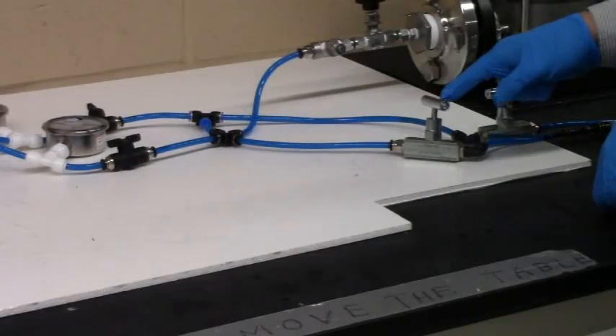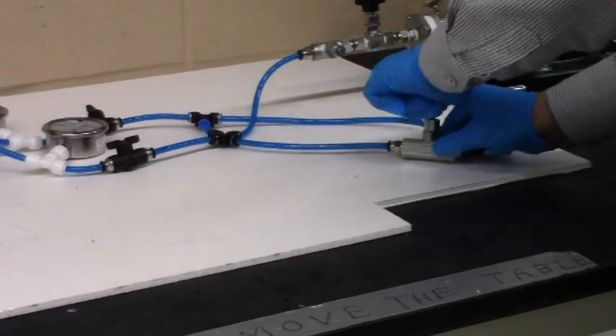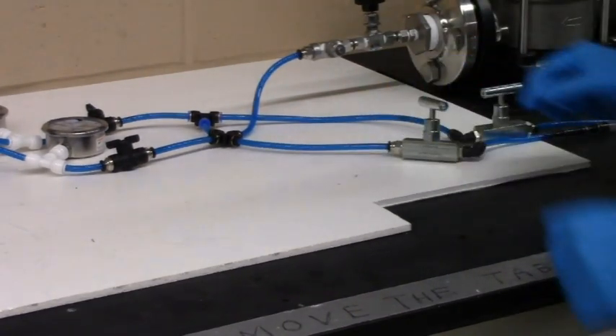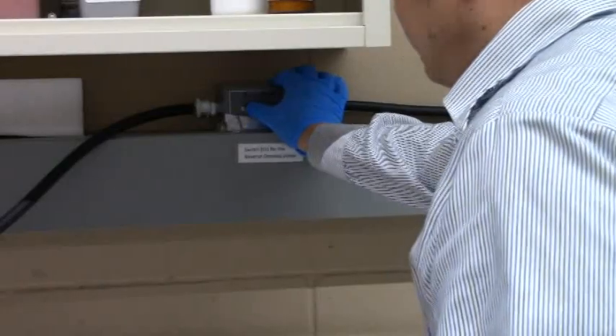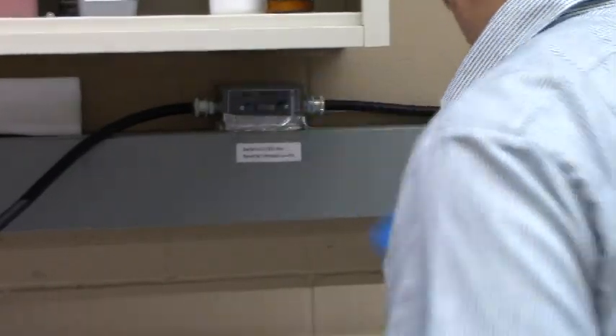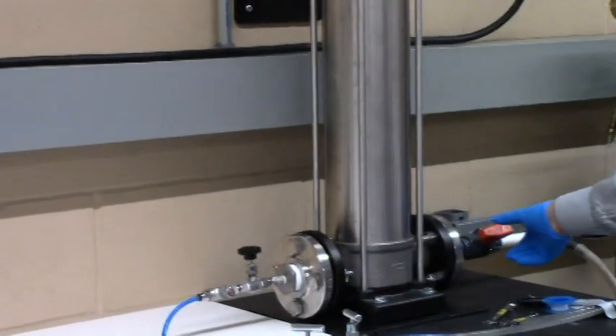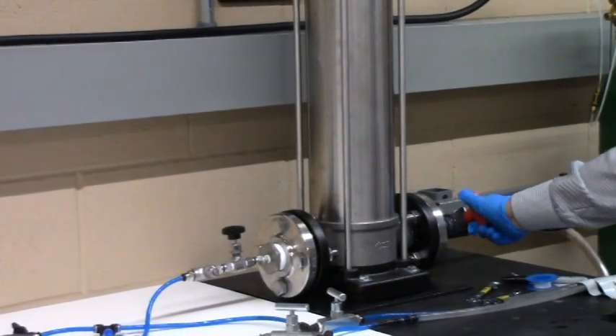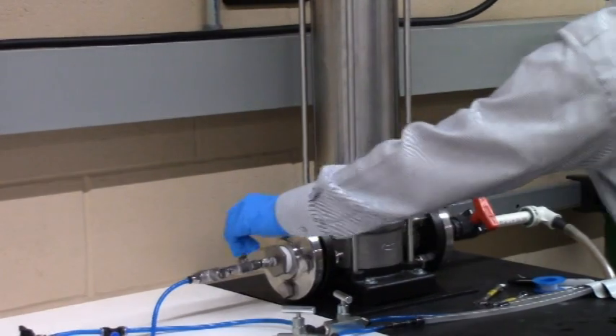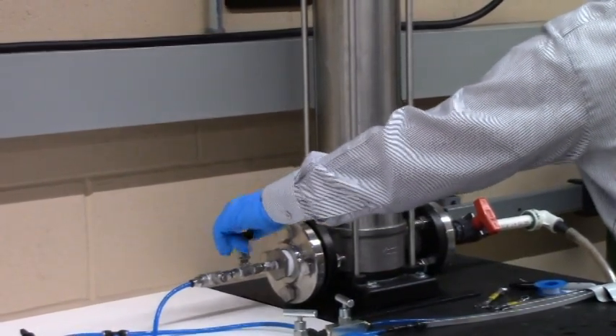When you achieve the pressure and TDS reading goals, open the bypass valves to flush the bypass valves with fresh water. Turn off the centrifugal pump by flipping the switch, and immediately after that, close the pump suction valve and then pump discharge valve.